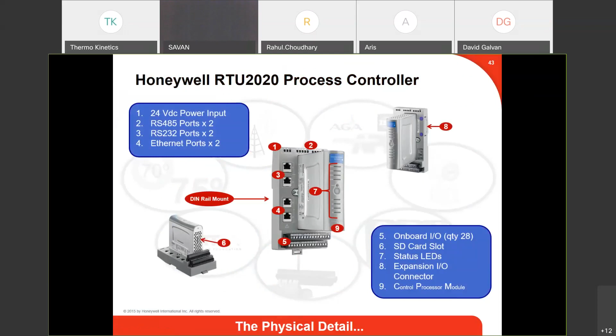It's really cool too when it comes to firmware upgrades with the RTU. If, for instance, I want to upgrade the firmware, I do not have to wait there. We all know that flashing the firmware can have its flaws, right? So if there's an interruption, you can break the unit. So many things can happen. Now, the way we manage that is when we want to upgrade the firmware for whatever reason, remember that this is in a remote area with a slow network - you never know the situation there.